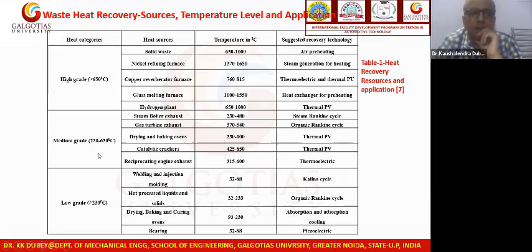Now the medium grade heat category and heat sources: here we can see steam boiler exhaust, gas turbine exhaust, and especially the reciprocating engine exhaust. Here the exhaust temperature is about 300 to 600 degrees C. Now this is a very important input for us to produce cooling without any consumption of extra energy, without any consumption of fuel, and without any extra consumption by a mechanical compressor. So the reciprocating engine exhaust and its heat utilization is considered under the medium heat grade recovery sources.